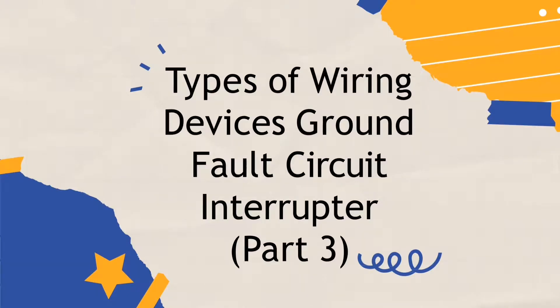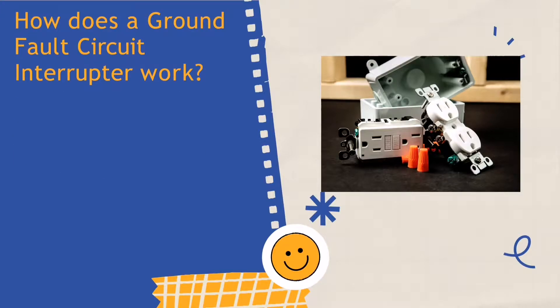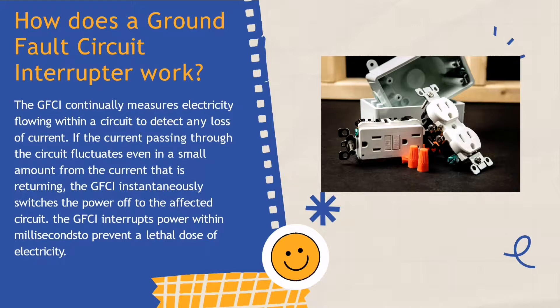Our topic for today is about types of wiring devices: ground fault circuit interrupter. Let us first know how does GFCI work. The GFCI continually measures electricity flowing within a circuit to detect any loss of current. If the current passing through the circuit fluctuates, even in a small amount from the current that is returning to complete the circuit, the GFCI instantaneously switches the power off to the affected circuit.